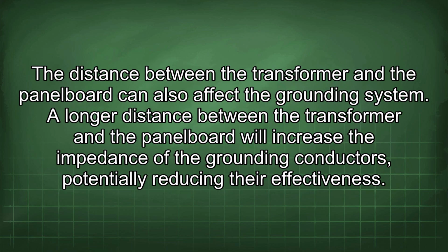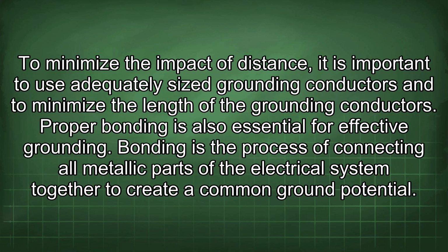The distance between the transformer and the panelboard can also affect the grounding system. A longer distance between the transformer and the panelboard will increase the impedance of the grounding conductors, potentially reducing their effectiveness. To minimize the impact of distance, it is important to use adequately sized grounding conductors and to minimize the length of the grounding conductors.